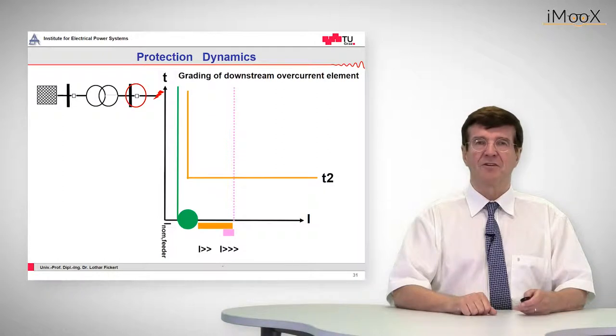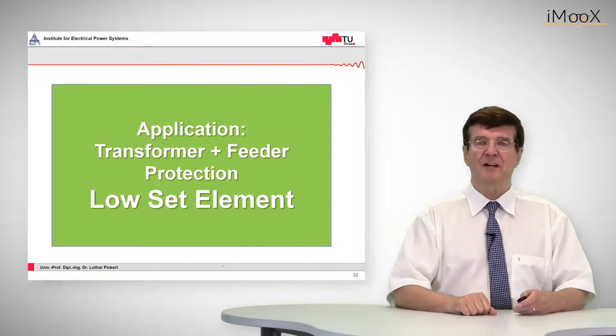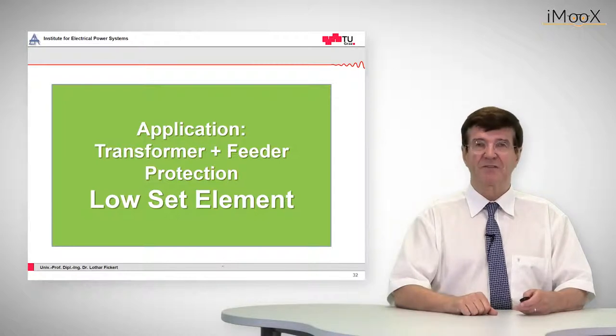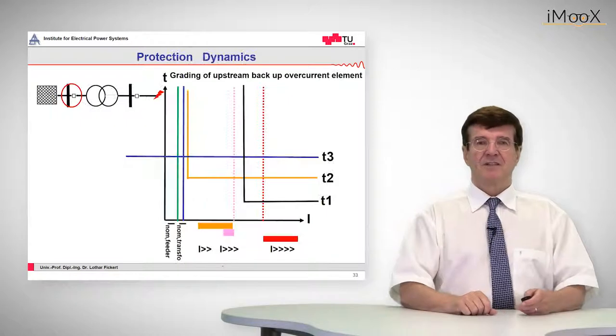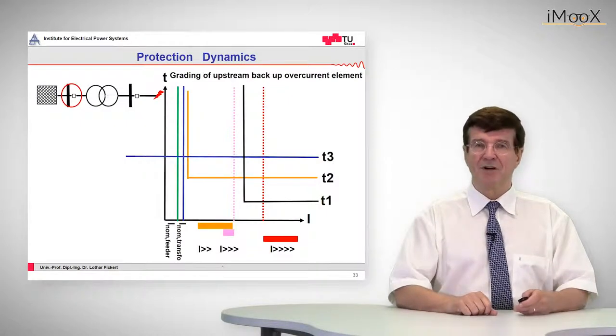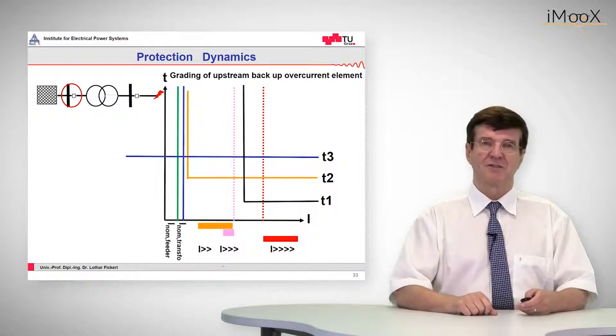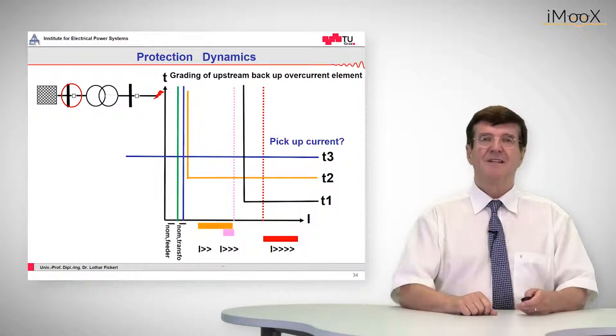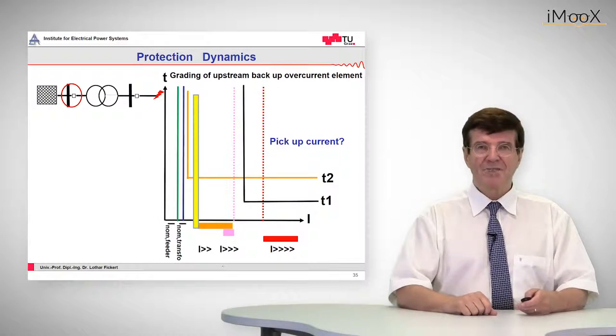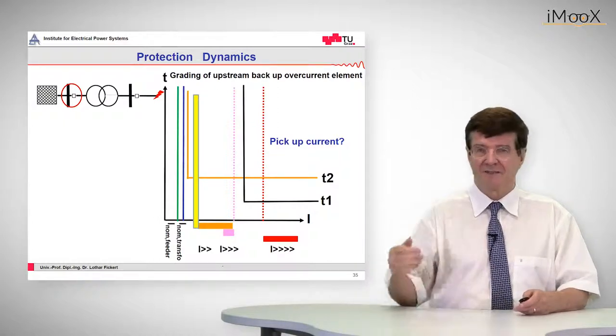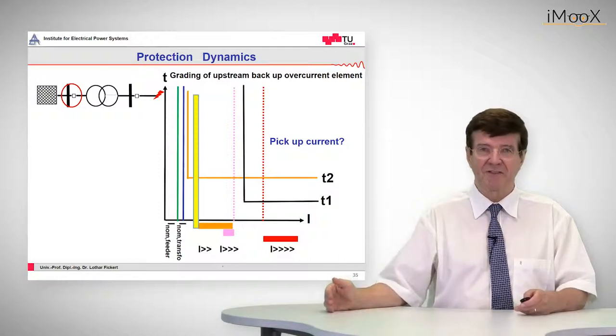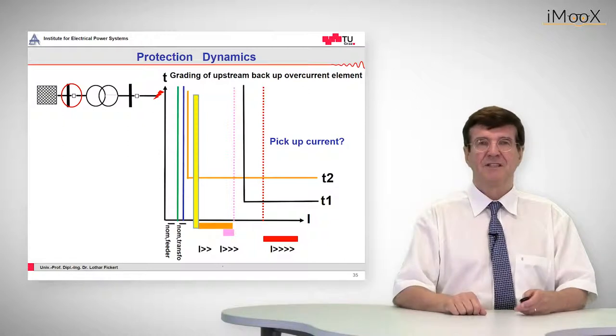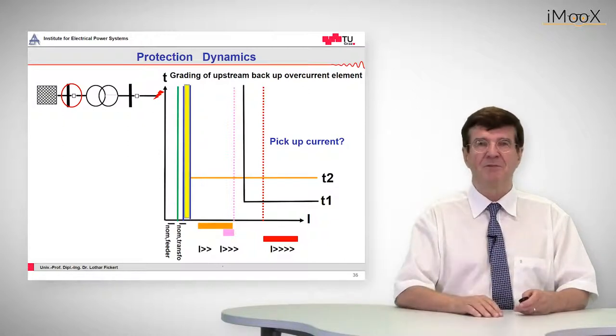This is the setting of the feeder protection downstream. We can also use an additional function of the upstream overcurrent protection as a backup protection — it should pick up if the feeder protection does not trip the fault. The tripping time is clear: it must be above the tripping time of the feeder, and this new tripping time is called T3. As for the pickup current, it should always pick up for the worst backup case, which is the short circuit at the far end of the longest feeder, so it must be set below that value. On the other hand, it should be above the maximum nominal current of the transformer in order not to impede normal operation.